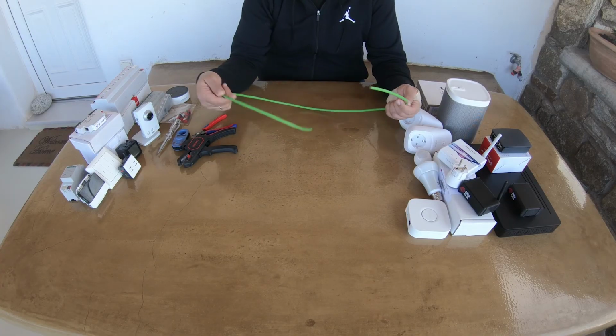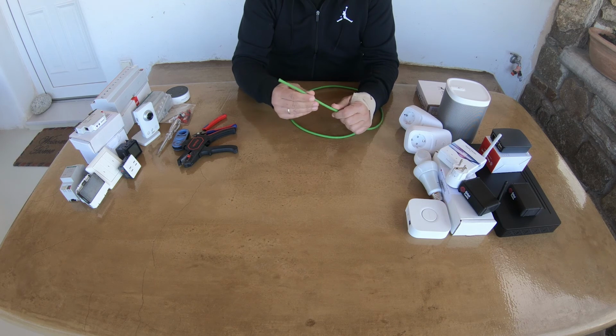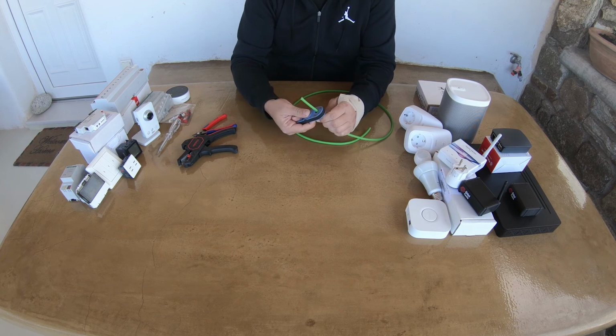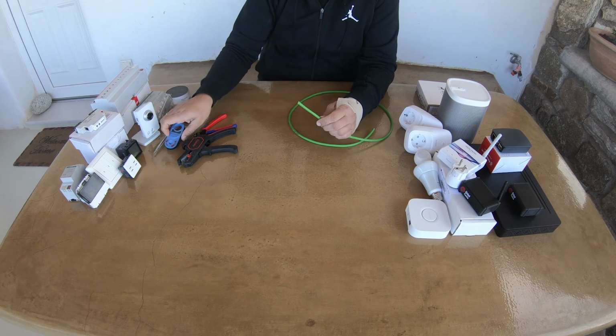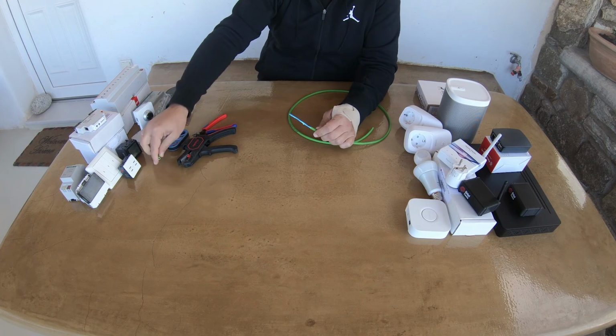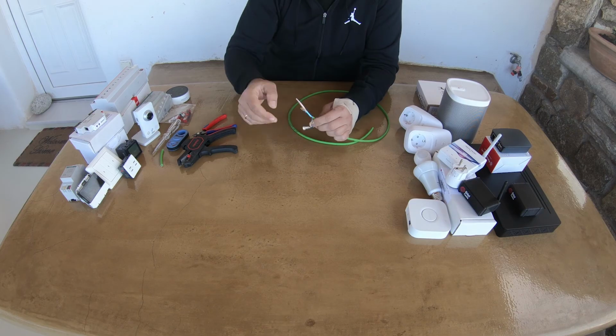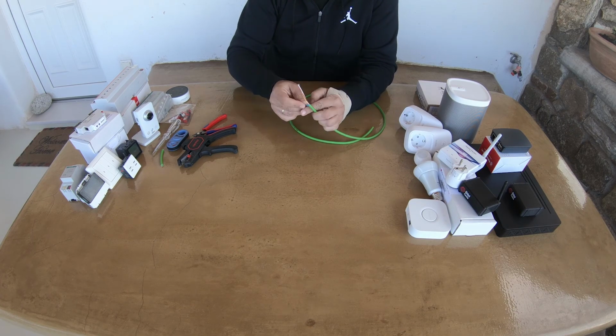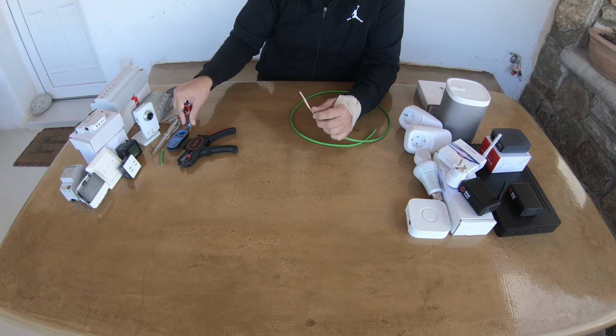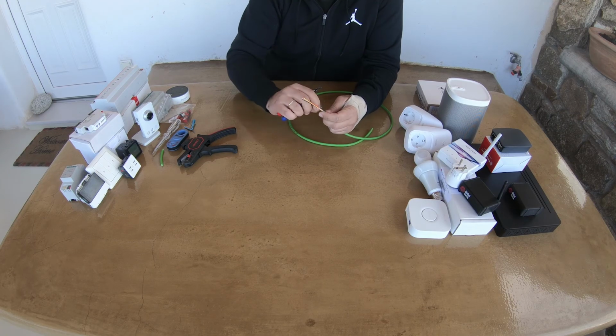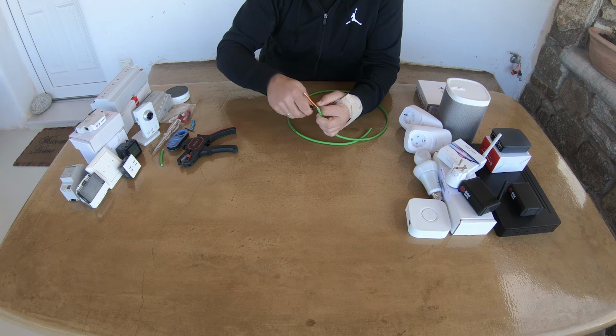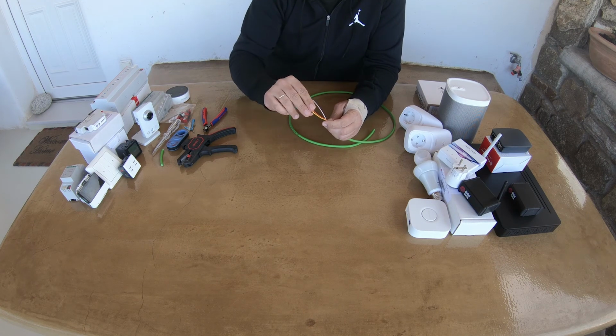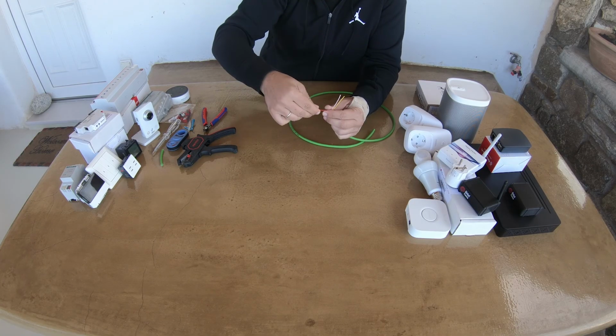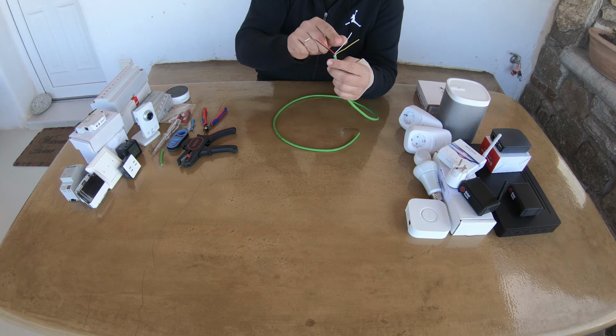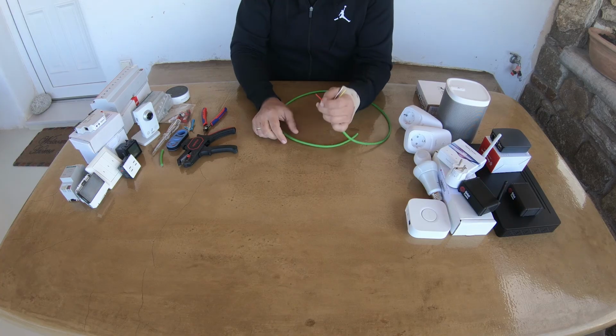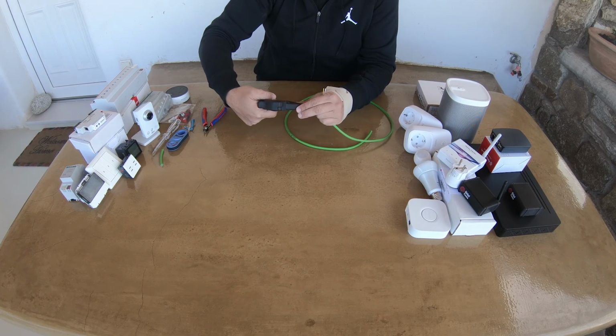Finally, let's speak about KNX bus cable. This is a bus cable. Let me show you now what is inside that cable. As you can see, there is a red and black cable that are used in all KNX connections and a yellow and white cable that can be used, for example, in order to supply a KNX device with additional external power.